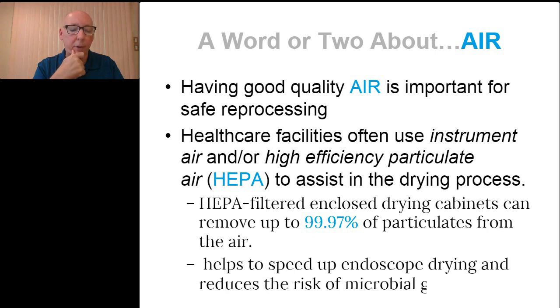Again, make sure that you're taking a look at both the filters in your drying cabinets and other devices. There may be other devices that you're using to blow out air or to dry devices that may have a HEPA filter. Make sure that you're checking the IFU from that manufacturer to make sure that HEPA filter is replaced appropriately so it's working for you. Those two filters work hand in hand to provide that clean air within your drying cabinet or other devices that have HEPA filters. So make sure that you follow accordingly and change those filters when you're supposed to.